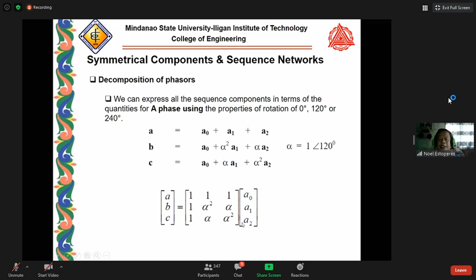For the network equations for the sequence components, this is what will happen. The generated voltages in the transmission system are assumed balanced prior to the fault, so that we can place this E sub F here, or we can solve for the sequence voltages in terms of the sequence currents. So I took, like in this case, our VA0, or the zero sequence voltage, is equal to negative Z0 times IA0.